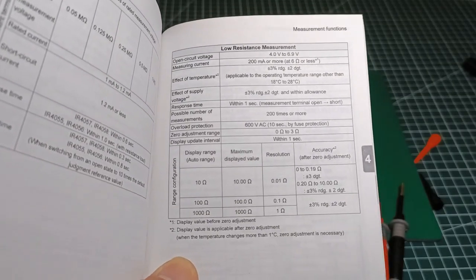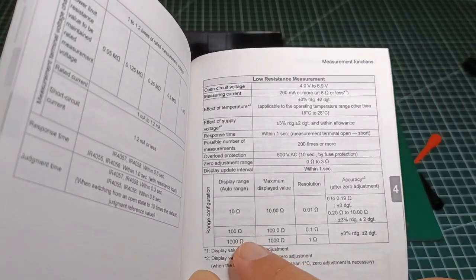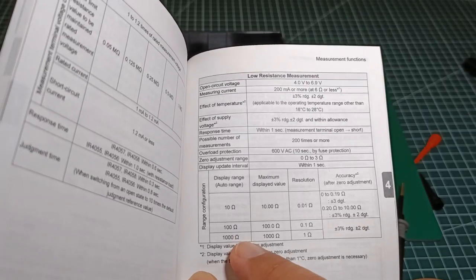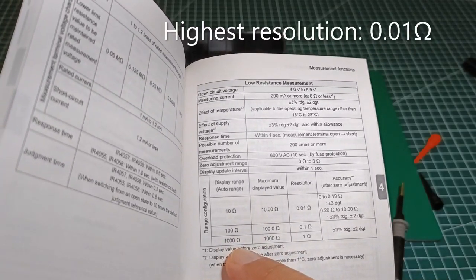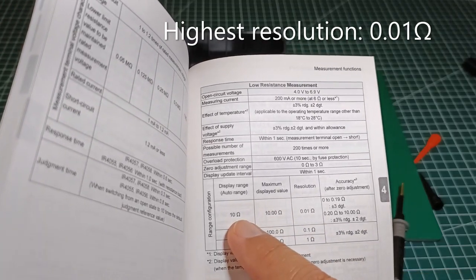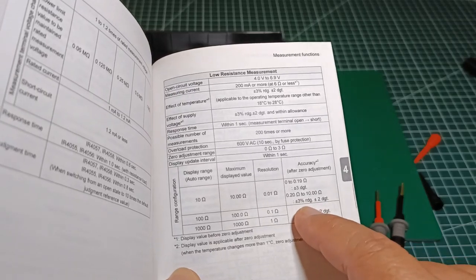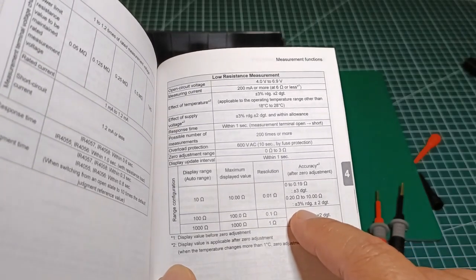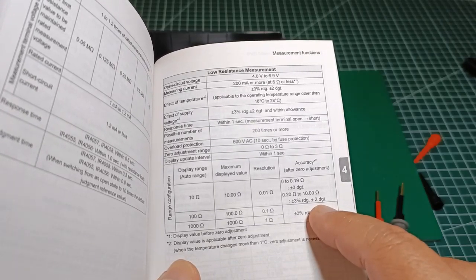Here at its user's manual, we can see that at the low resistance measurement, the instrument has three automatic ranges: 10 ohms, 100 ohms, and 1000 ohms. The highest resolution can be found in the 10 ohm range, which is 0.01 ohm, with an accuracy of plus or minus 3 percent of the reading and plus or minus 2 digits.